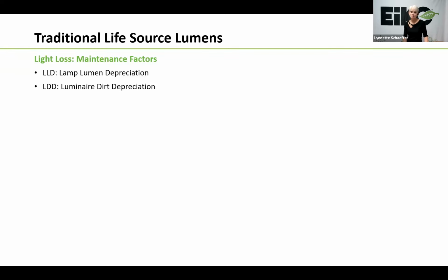Anyways, something else that contributes to a loss of lumens on the work surface is luminaire dirt depreciation. That means that the fixture and the lamps get dirty and the light just can't penetrate through the dust and the dirt. As a matter of fact, let's say you have a customer that installs a 6-lamp T8 linear high bay. Say they put a lens on it and it's an industrial application. According to the spec sheet, those lamps were rated for 2,850 lumens. You multiply that by 6, that means it should have been producing 17,100 lumens.